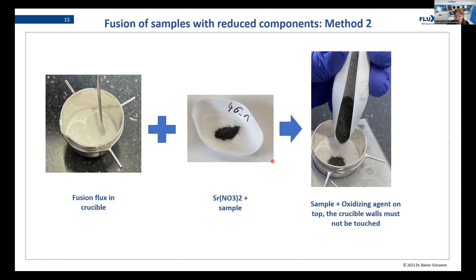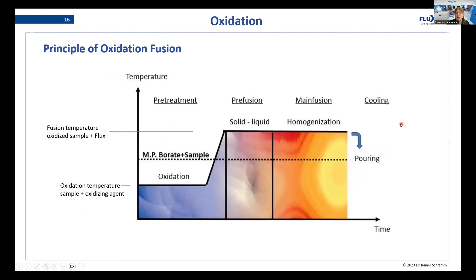When the oxidizing mixture touches the crucible walls, you end up with the same problem — damaged crucibles. This needs a little bit of practice to put it in correctly without touching the crucible walls. Then this crucible is ready to go, and you also need a special fusion program to have this oxidation happening in a safe way. You set an oxidation temperature below the melting point of the borate and sample, oxidize the whole thing, then increase the temperature so the borate and sample become liquid, homogenize, pour, and cool — giving you completely oxidized material in the fused bead.